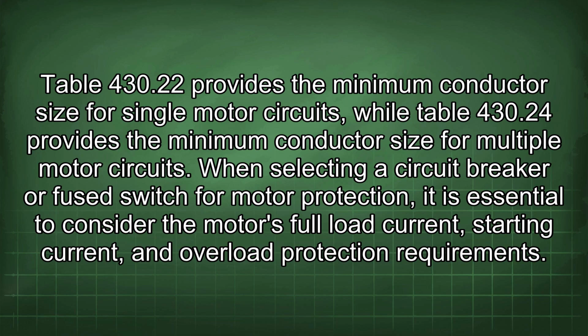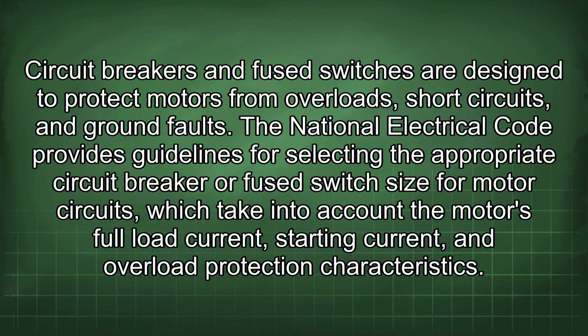When selecting a circuit breaker or fuse switch for motor protection, it is essential to consider the motor's full load current, starting current, and overload protection requirements. Circuit breakers and fuse switches are designed to protect motors from overloads, short circuits, and ground faults. The National Electrical Code provides guidelines for selecting the appropriate circuit breaker or fuse switch size for motor circuits, which take into account the motor's full load current, starting current, and overload protection characteristics.